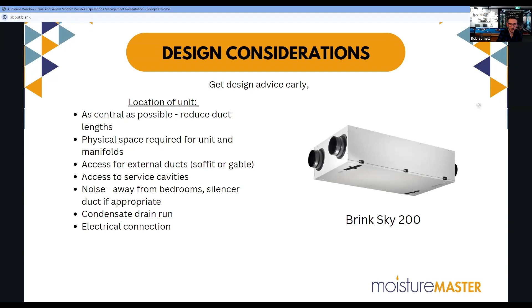Some further design considerations. We've got sizing of the unit. So we're looking at a combination of things to size the unit accurately. We're looking at the volume of habitable space times 0.35 air changes an hour. We're looking at number of occupants times 30 cubic metres per occupant per hour. We're looking at the extraction requirements for kitchens and bathrooms. And once we look at all of that, we then balance the system to the highest need of those. And then we include 30 to 40%, sometimes even a little bit higher, capacity within the system. So if we do need extra ventilation, then we've got it there rather than trying to skimp on it.